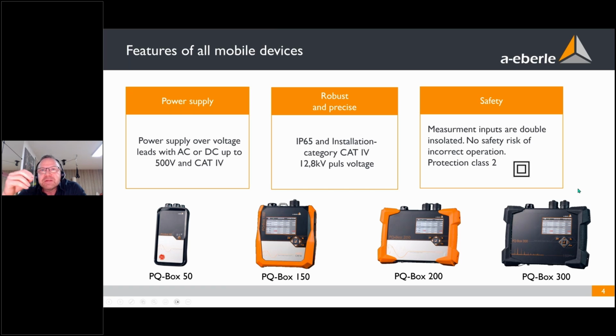So if you make some faults and connect some voltage to the earth, to the green line of the analyzers, even here we can withstand up to 500 volts. You can do whatever you want. There's never a safety risk. If you do the same with a fixed installed device, you have this voltage of the earth directly on your interface. So it's a risk for your PC equipment and also for the human who is using this. So be aware, there's a big difference between using fixed installed and mobile analyzers if you do it this way. With mobile analyzers, normally there's no risk because there's protection class 2. The device itself does not know what the earth is.